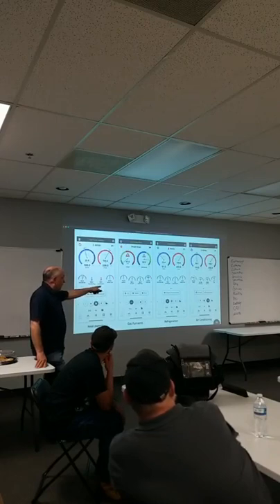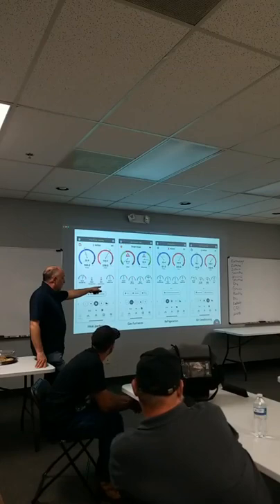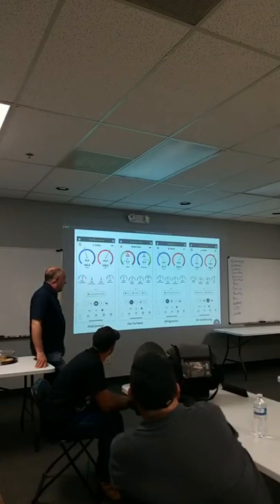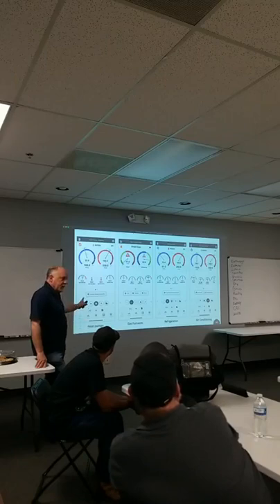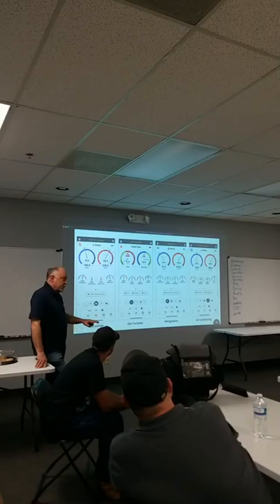Measurequick does do refrigeration. We have a pretty cultish following for the refrigeration side, the gas heating side, and we can do heat pumps in the heating mode. The thing with heat pumps in the heating mode is no matter what you do, this will get you in the ballpark, but you have to go back and check the charge in air conditioning.